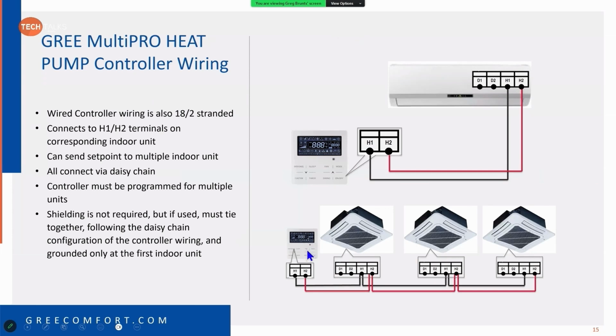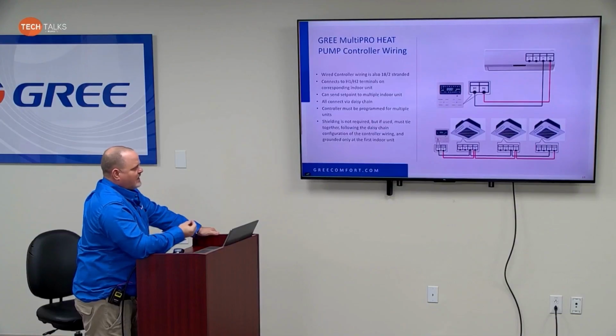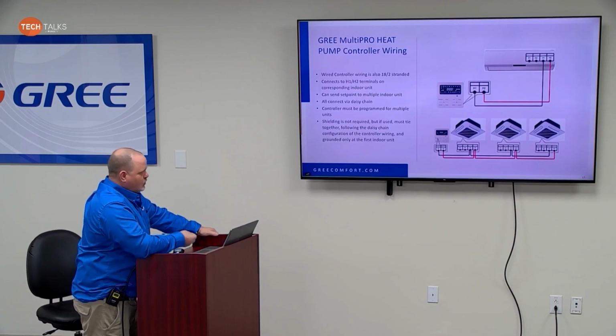But you have to go into this controller, and it'll ask you for the number of IDUs. A lot of guys get that confused. They think that's the number of IDUs on the system. The controller is not asking you how many indoor units are on the system. It is asking you how many indoor units it is controlling. The new XC7C controller, we actually had them change that, and it will say number of indoor units controlled by controller.